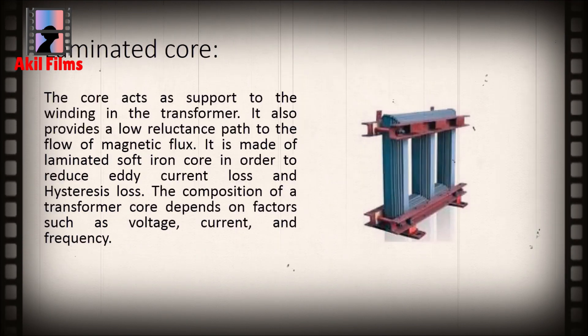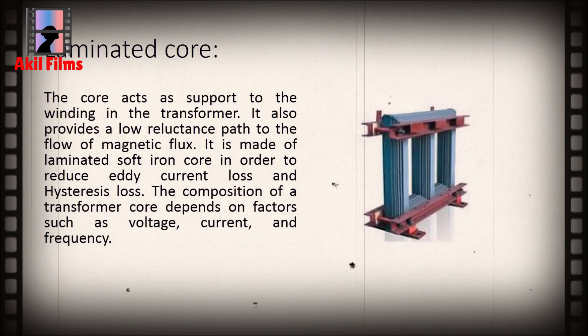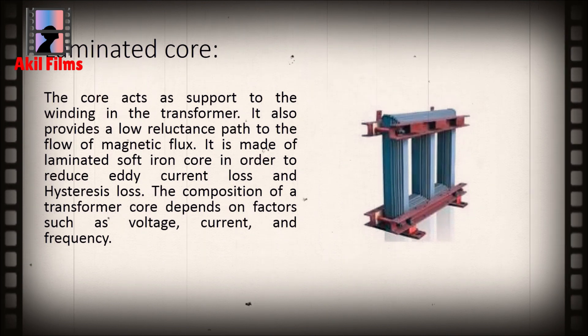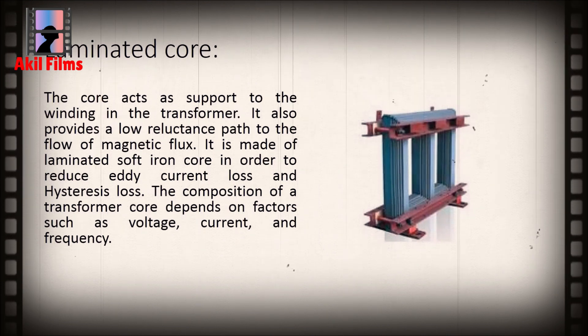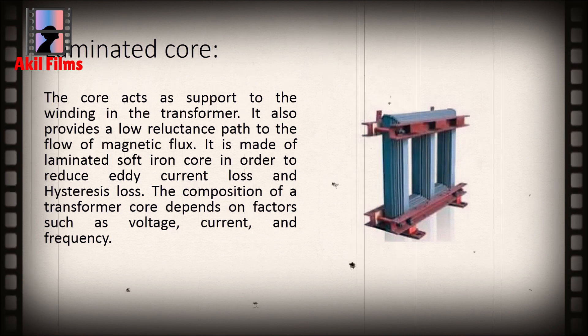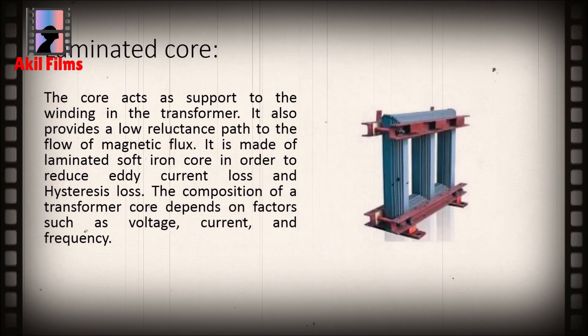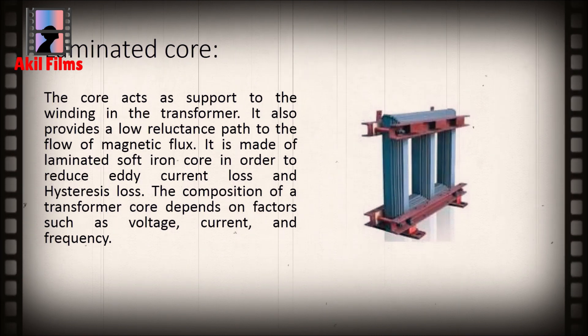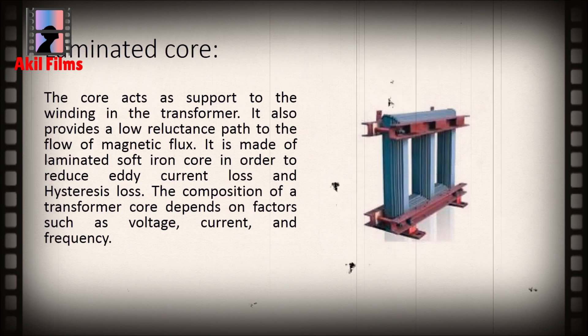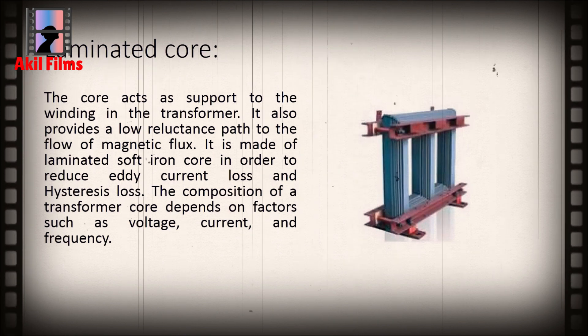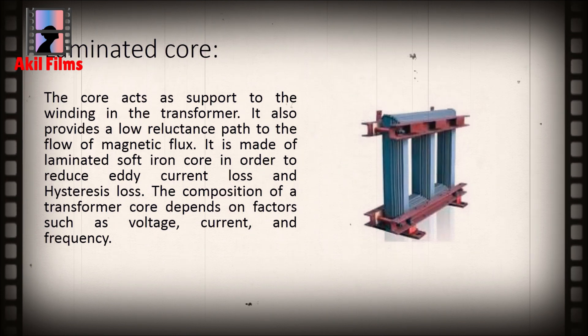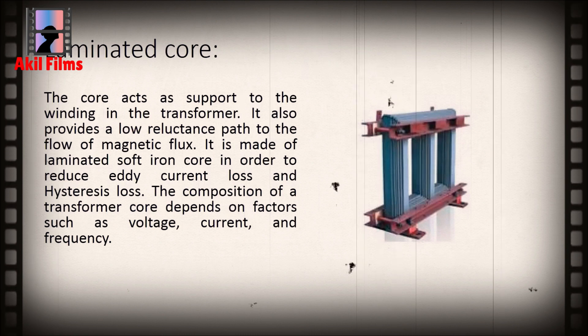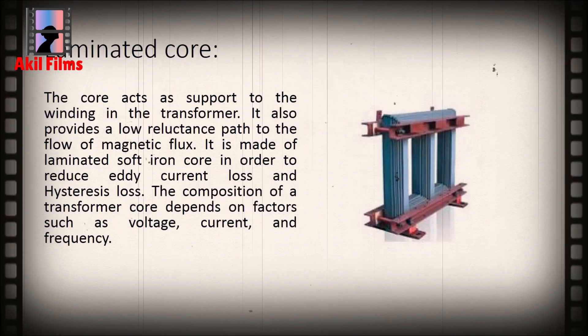The core acts as support to the winding in the transformer. It also provides a low reluctance path to the flow of magnetic flux. It is made of laminated soft iron core in order to reduce eddy current loss and hysteresis loss.